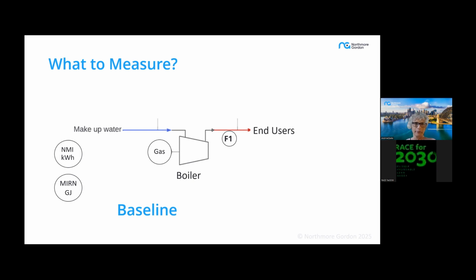And in terms of your system design, again, it's important to understand your heat demand. So your gas can give you a reasonable understanding of your heat demand, but generally there's a hot water tank involved in association with a hot water boiler. So the demand profile can actually be a little bit different to what you see in your gas consumption. And so understanding the flow of hot water and also the amount of heat that is put into the water, so temperature before and after the boiler.